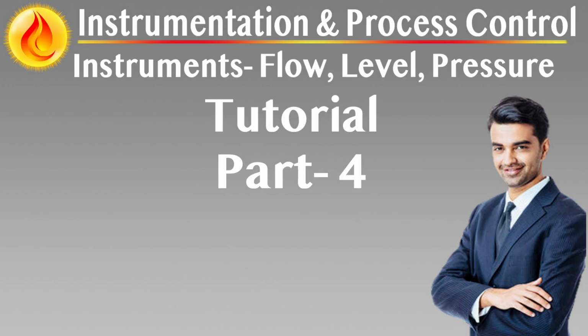The orifice bore should be calculated based on actual process data and then rounded to a standard size for ease of maintenance and spare parts management. Primary element options and use cases. Square edge orifice plates, common and cost-effective, suitable for clean single-phase fluids. Venturi tubes, lower permanent pressure loss, ideal for larger lines or erosive services. Flow nozzles, better suited to high-velocity, high-pressure services. Restriction orifice plates, not used for flow measurement, but to limit flow or reduce pressure.